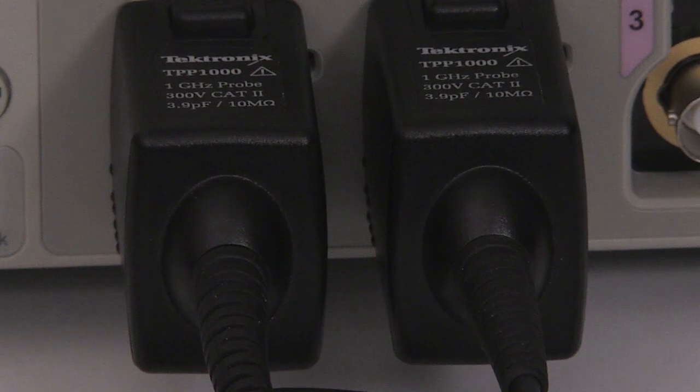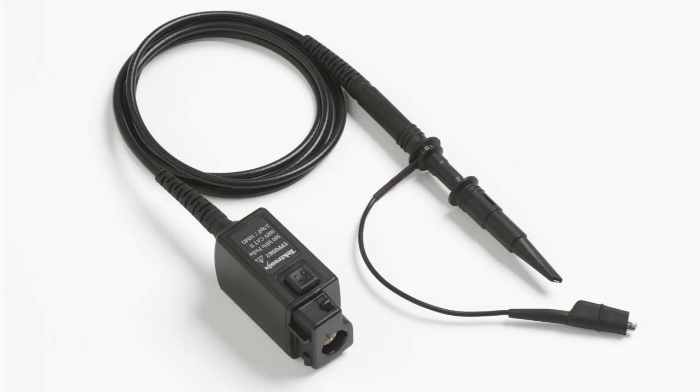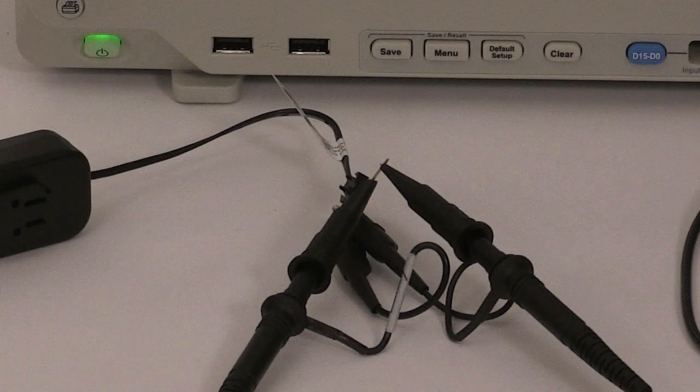In fact, for those interested, there is a similar 500 MHz 2X probe. Less signals attenuated so you get a better signal-to-noise ratio with better resolution than the competitors' 10X probes.